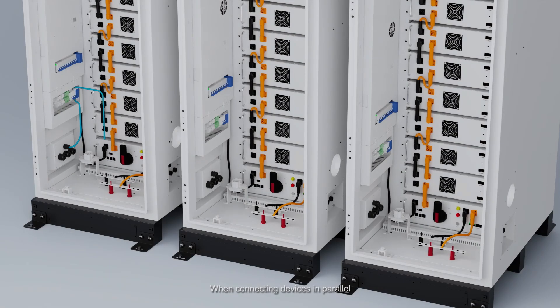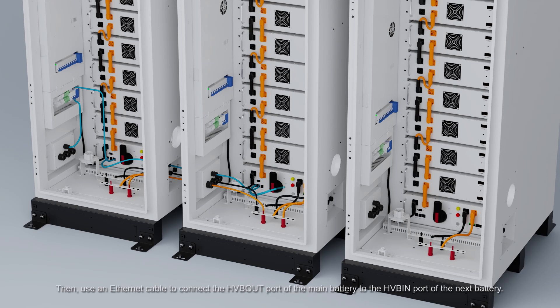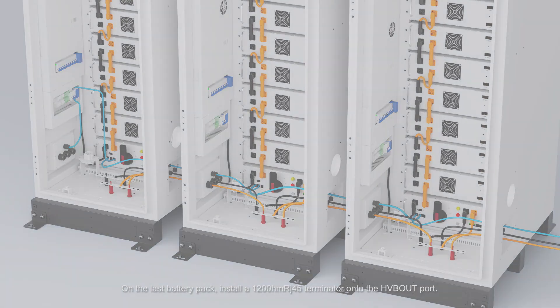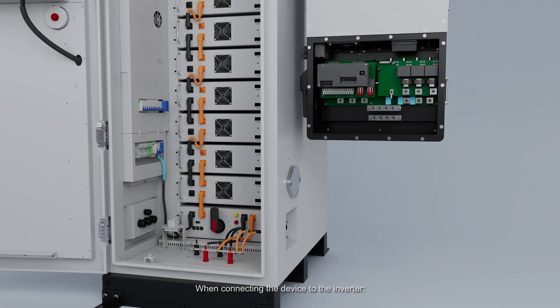When connecting devices in parallel, use the positive and negative power cables to sequentially connect the subsequent battery packs. Then, use an Ethernet cable to connect the HV-Bout port of the main battery to the HV-Bin port of the next battery. On the last battery pack, install a 120Ω RJ45 terminator onto the HV-Bout port.